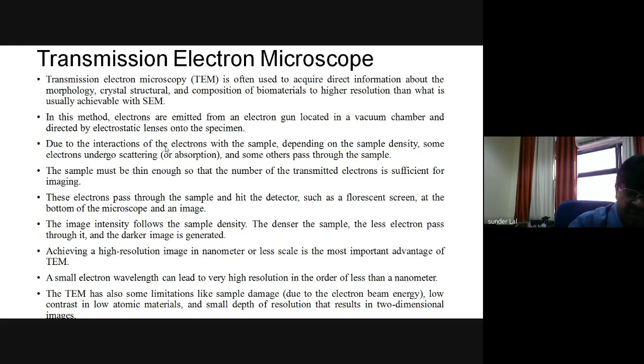Another important point is that TEM also has some limitations. Because the sample can get damaged. Why does the sample damage happen? Due to the electron beam energy, low contrast in low atomic number materials, and a small depth of field that results in two-dimensional images. So these are the basic features of an electron microscope and its limitations. What I mean is the damage of the sample.